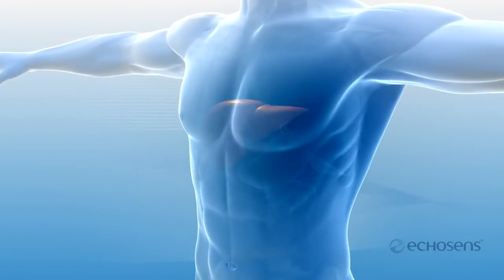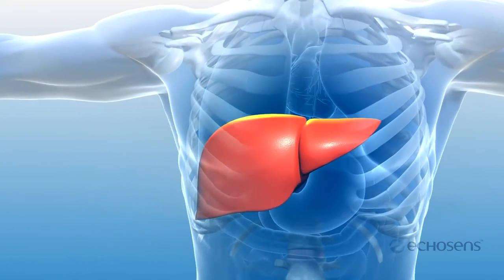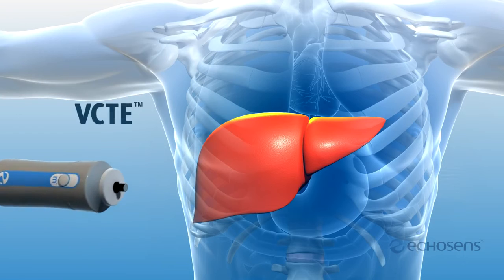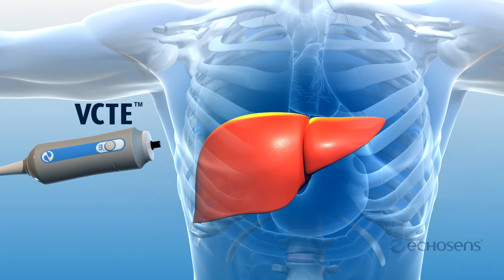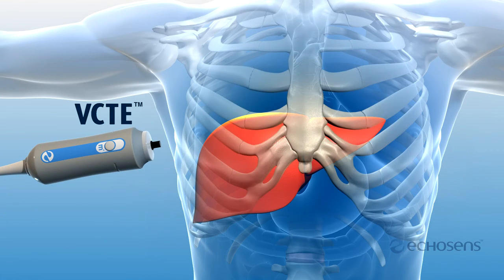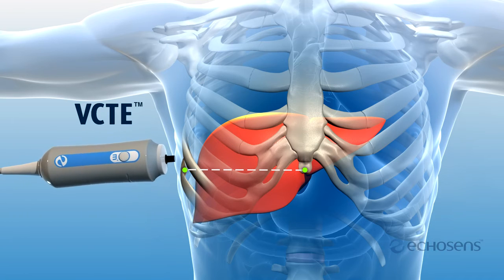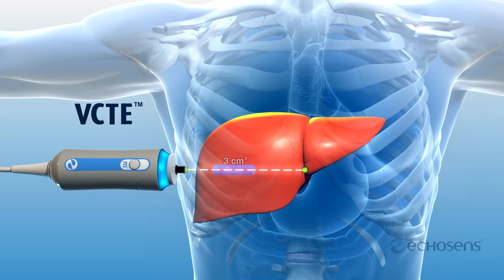FibroScan is powered by vibration-controlled transient elastography, or VCTE. Here is how this unique method for assessing liver stiffness works. A 50 Hz shear wave is mechanically induced from the tip of the FibroScan probe. To the patient, this feels like a slight flick or tap on the skin.